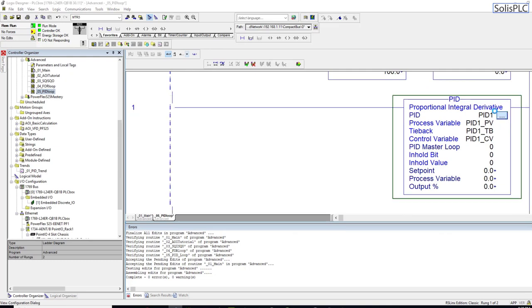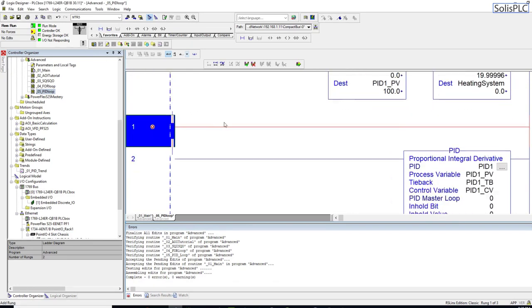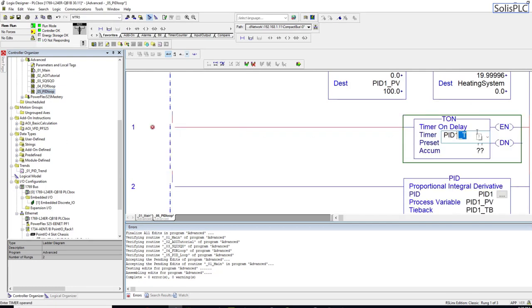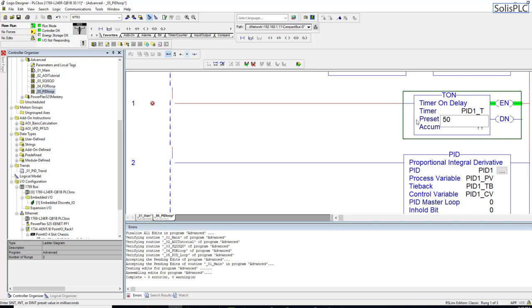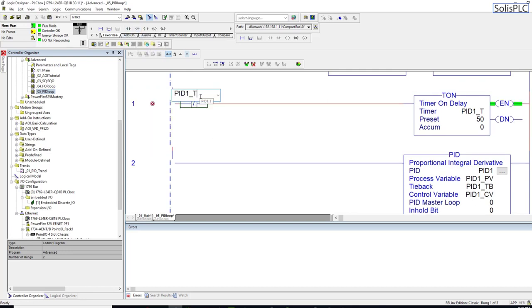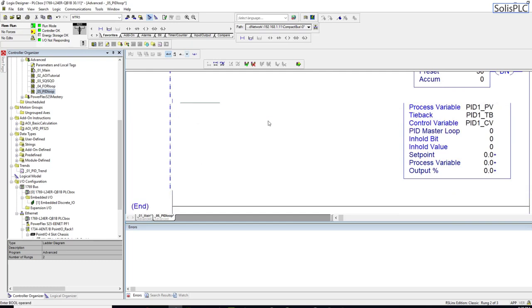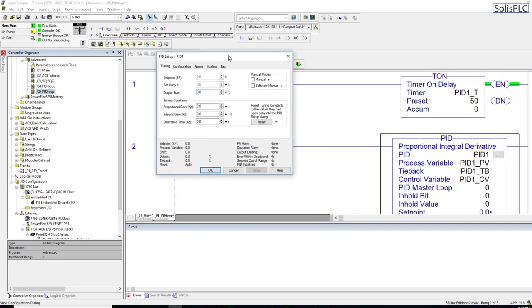We also need to create a timer that will update our loop. I'll create a TON instruction called PID1_T, updating every 50 milliseconds. The timer cycles on itself using an XIO instruction tied to the done bit — think of this as a repeating timer. Once the timer is done, the PID loop updates.